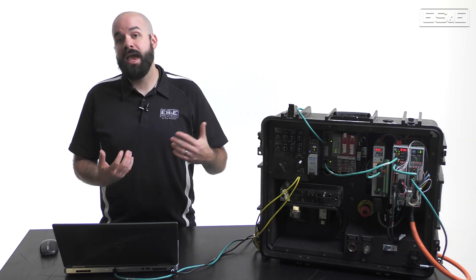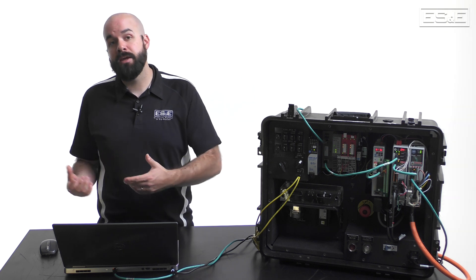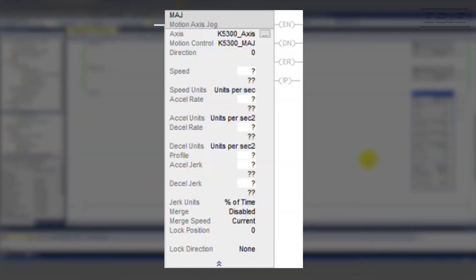Now let's enter those calculated values into the MAJ fields. Our target speed is 360 degrees per second. With jerk set to 50% of time, the acceleration needs to be 480 degrees per second squared. Because we're not using this MAJ to reduce the speed of an already running move, the Decel field here is meaningless. However, we still need to put a value in the field, so we can just use the same rate we used for Accel.